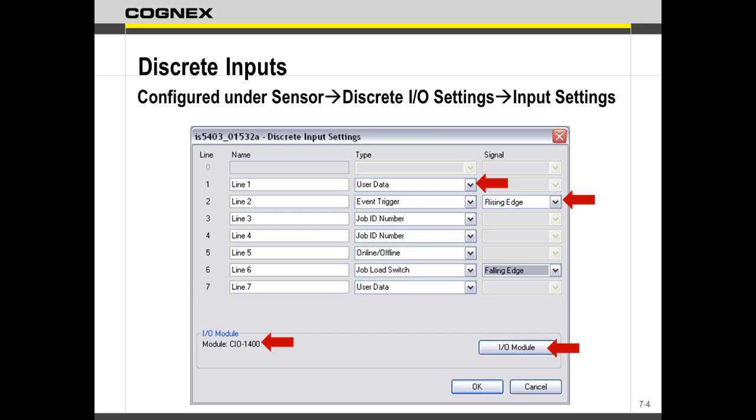So now what happens is your PLC is going to put that number on there. If I have 6, I could have my job saved inside memory as like 0_my_job, 1_Yahoo, 2_let's_get_going, 3_Friday_is_awesome, whatever you want to call them, but you're putting a number in front of it. It's going to resolve that number first, and as soon as it starts getting to the alpha characters, it ignores those. So just that number in the beginning. It's got to be in the beginning, not the end.